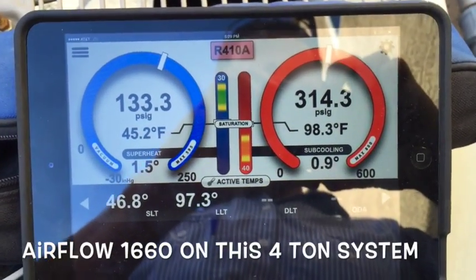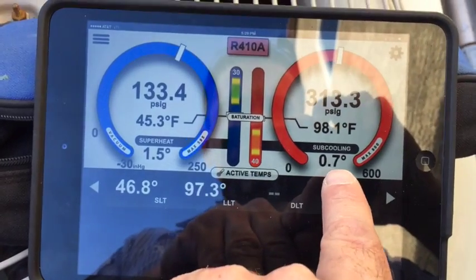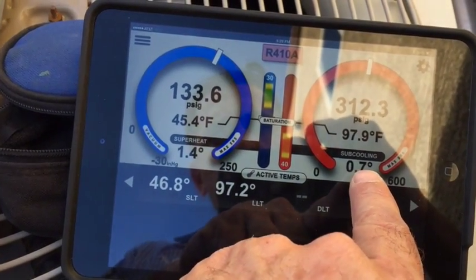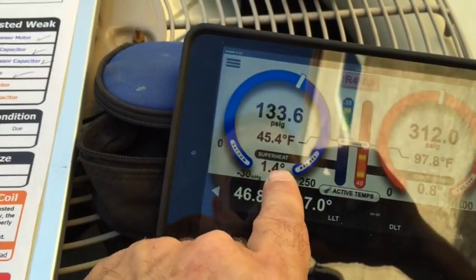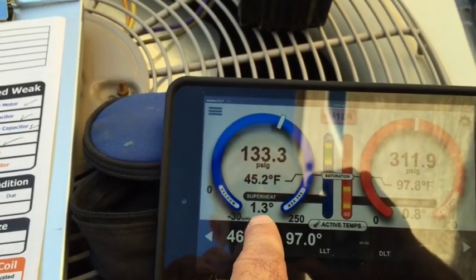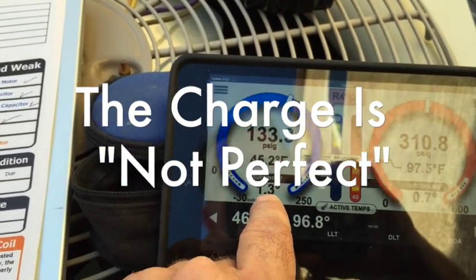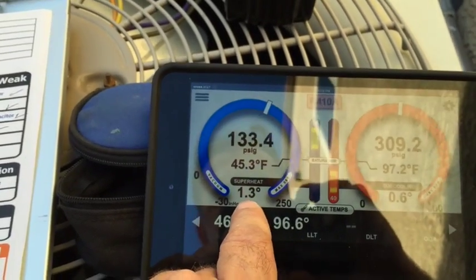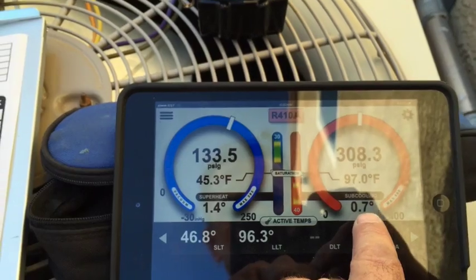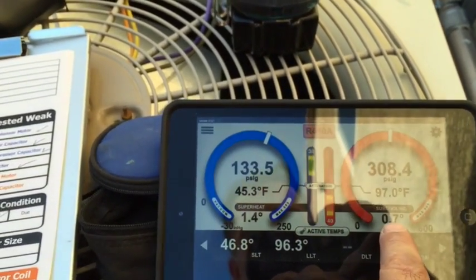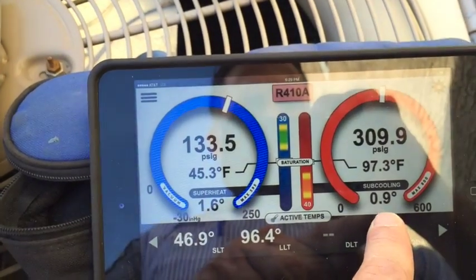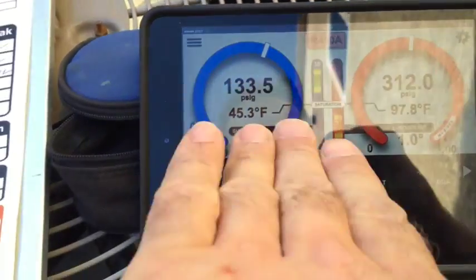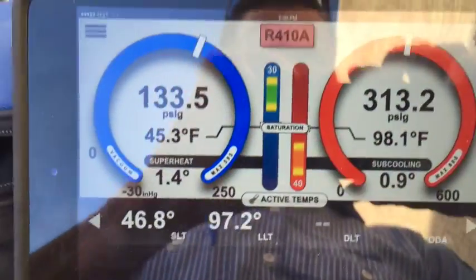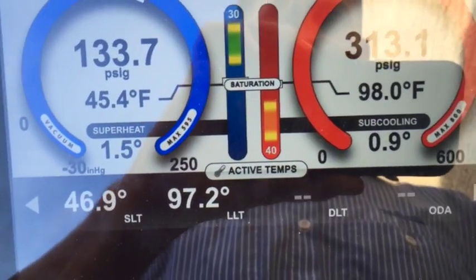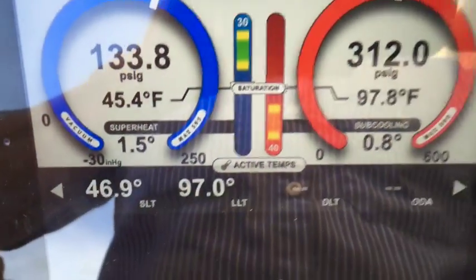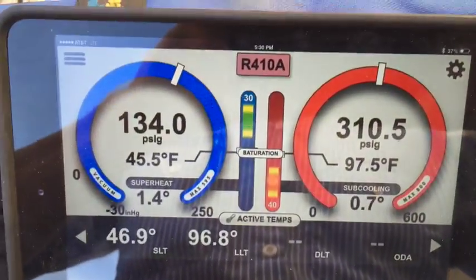So, according to these pressures, my subcooling is low, and I can't seem to get it high enough. My superheat is low also. So if I add refrigerant, it's going to go lower. Not what I want. So this is telling me to take away refrigerant, while my low subcooling is telling me to add refrigerant. Now, that tells us that the problem is not refrigeration, or I should say it's not a charge issue, over or under. It's either airflow, which we're going to go ahead and cross out due to our history in this home and what we already know.